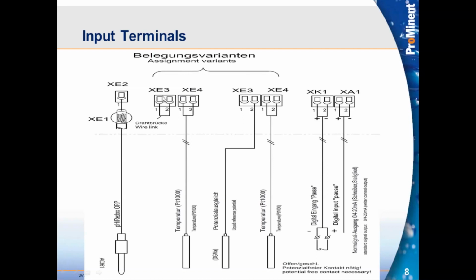Then we have some varieties between XE3 and XE4. Here, XE3, just like we saw in the picture, is jumpered. And then we have our temperature sensor to XE4. I mentioned the reference sensor, XE3. So remember, those sensors, the pH sensor as well as the ORP sensors, are measuring millivolts, very small voltage signals. If there is any electrical noise that gets picked up in the water, which can be common, we want to use that as our 0 point, and that number is probably going to be changing. So as it changes, we need to know about it.